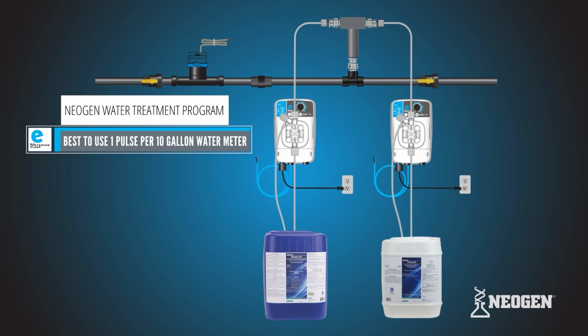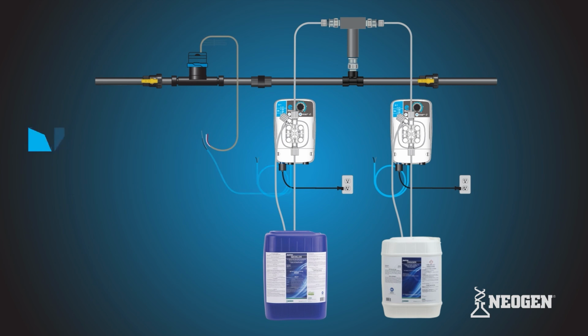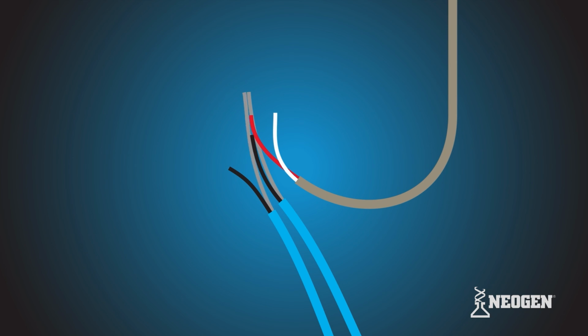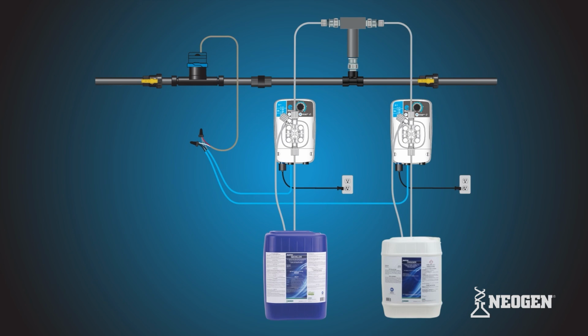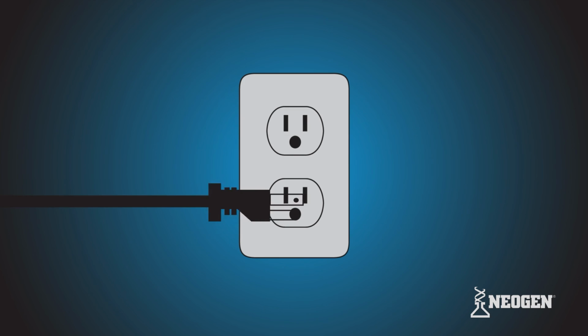Now that your second pump is installed, it is time to connect your pumps to the water meter. Grab the eMP and water meter lead wires. Connect one wire from each pump that are the same color with one of the water meter lead wires. Now connect the rest of the remaining wires together. After the wires are secured, both pumps should now be ready to connect to the power supply.